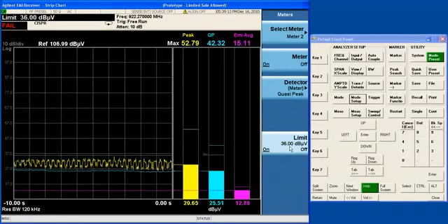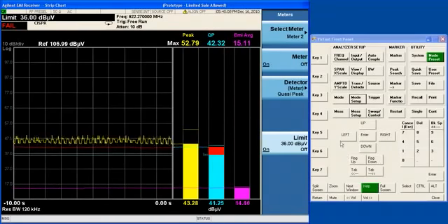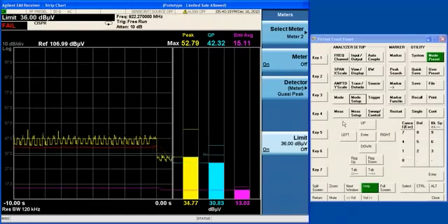And also, I can actually capture data for up to 20 minutes using the strip chart. So you can use the limits function basically to detect changes in the meters based on values that you set yourself. Now you can see that I'm only able to see 10 seconds of data right now given the current display settings, but I can actually capture data for up to 20 minutes.